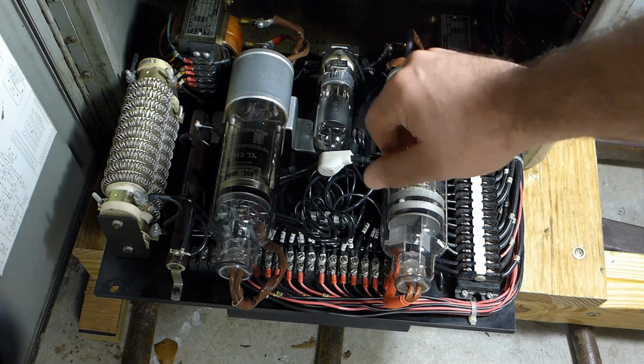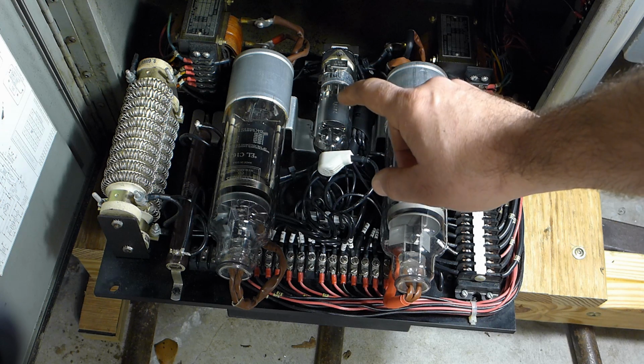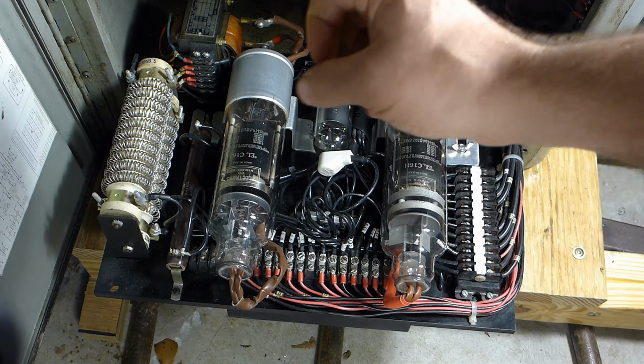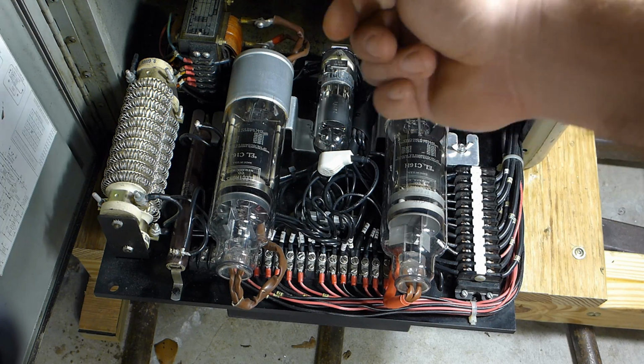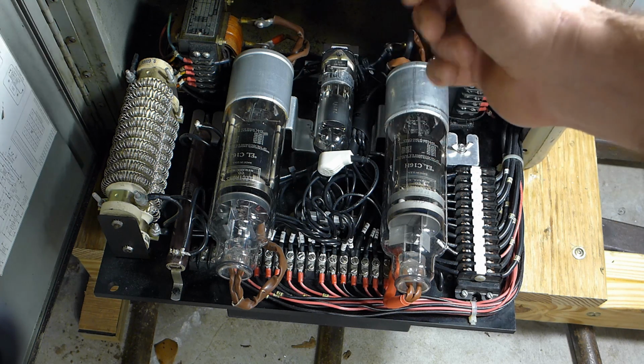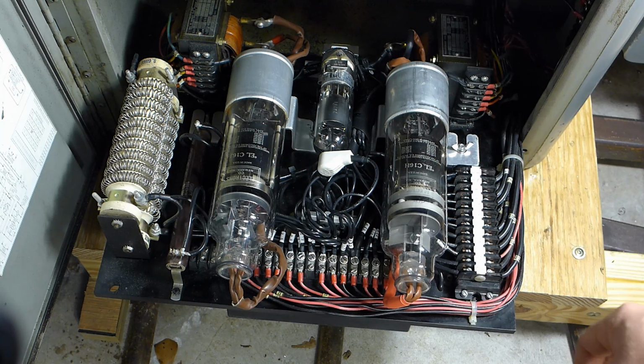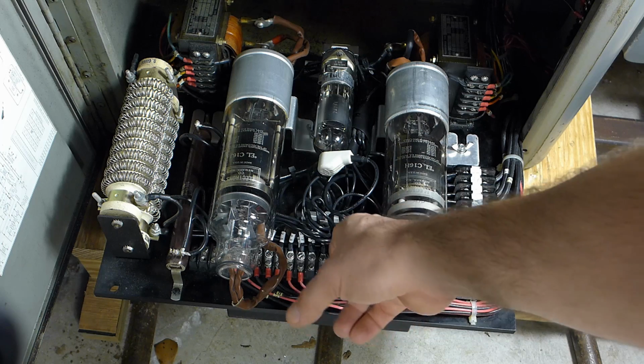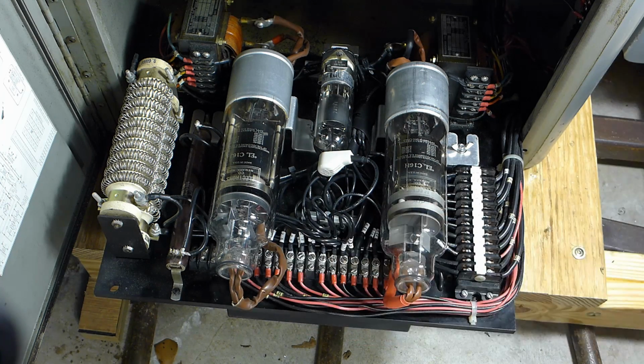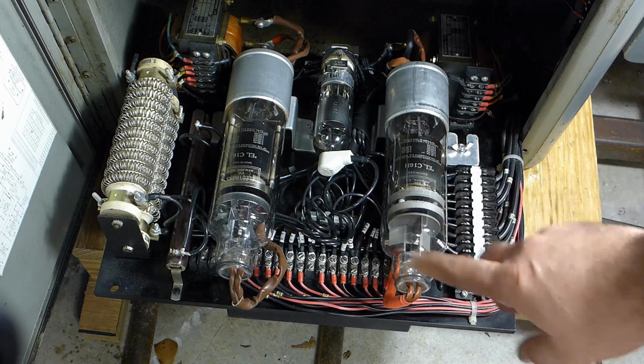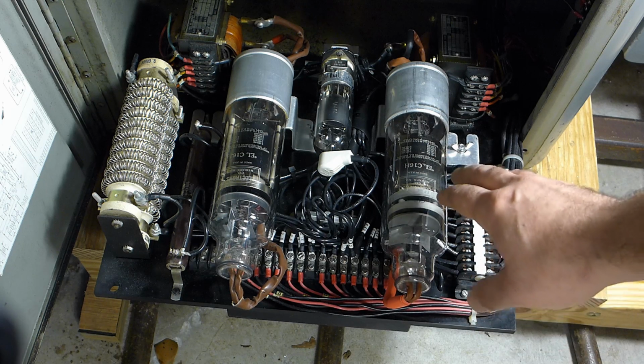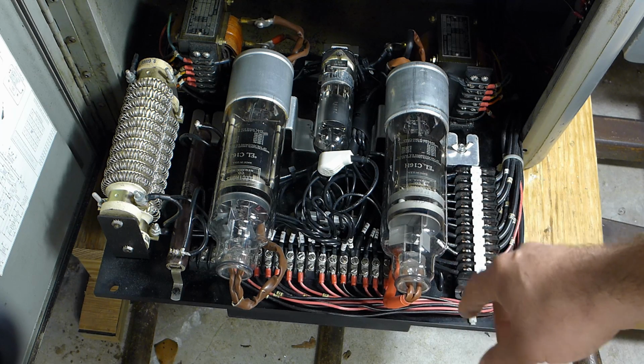The transformer back there is essentially triggering the two thyratrons, and one of the wires going to it was broken. One was completely detached, and the other one was broken inside the insulation so that it would intermittently make contact. The wire that I thought might be a concern, there was a lug under here that was tightened down onto another wire. That was not an issue, it didn't penetrate through the insulation.